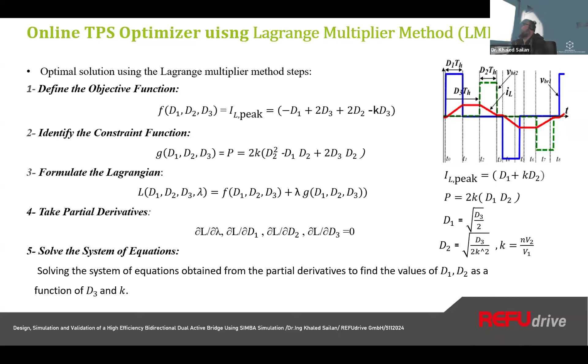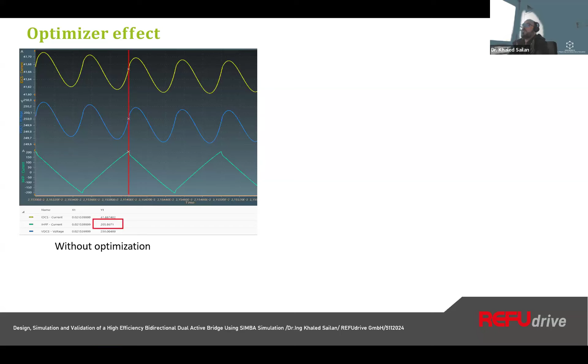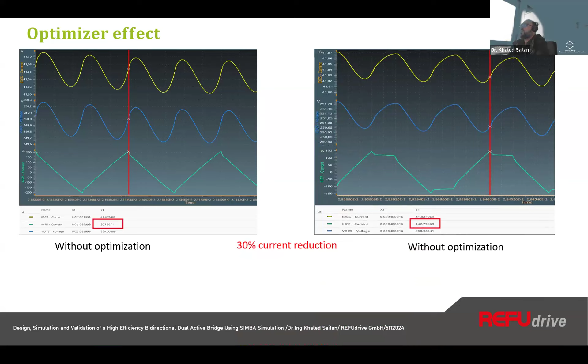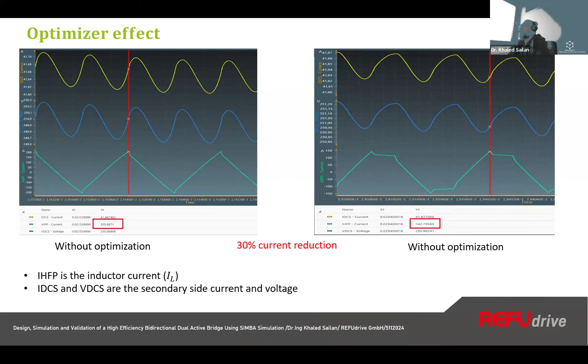You can see here the effect of the optimizer. If we work without the optimizer, on the left side, the high frequency current is around 205 amps. But if I apply the online optimizer, you can see I could reduce the current from 205 to 142, around 30% current reduction. So we could achieve a 30% current reduction in the best cases.